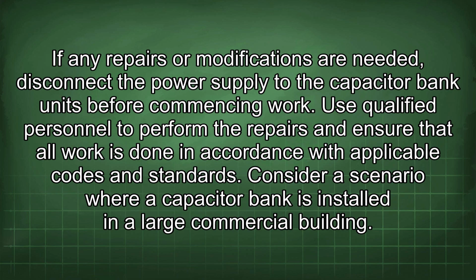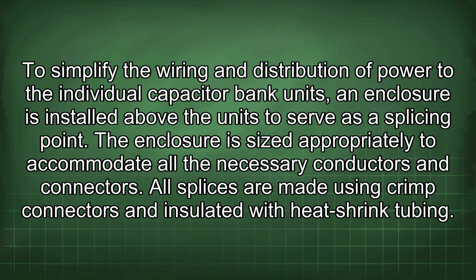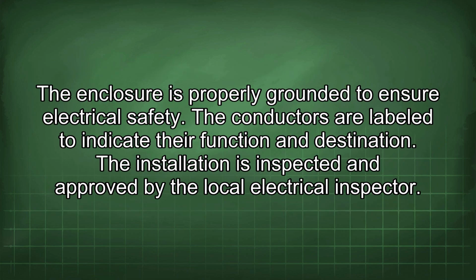standards. Consider a scenario where a capacitor bank is installed in a large commercial building. To simplify the wiring and distribution of power to the individual capacitor bank units, an enclosure is installed above the units to serve as a splicing point. The enclosure is sized appropriately to accommodate all the necessary conductors and connectors. All splices are made using crimped connectors and insulated with heat-shrink tubing. The enclosure is properly grounded to ensure electrical safety. The conductors are labeled to indicate their function and destination. The installation is inspected and approved by the local electrical inspector.